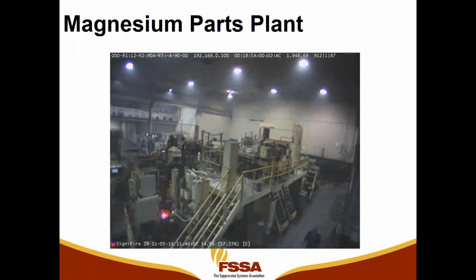So a difficult application for any technology is a plant where they make car parts out of molten magnesium. So in this view, the building is over 40 foot high. It's a smoky environment, and there's a flame normally in the process. So you wouldn't be able to use smoke detectors, heat detectors, or radiant energy detectors. So with video analytics, a camera is placed in the facility, record for about a week, go back and find the areas where there's a flame in the process.